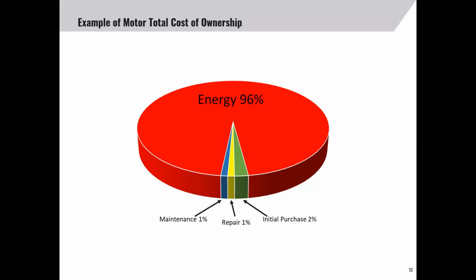There are no NEMA standards for motor efficiency for a manufacturer to meet. As the purchaser, you will be subject to a manufacturer's motor design and the efficiency of that machine. Many companies, when purchasing large horsepower motors, consider these purchases capital expenditures. Most motors above 500 horsepower can cost tens of thousands of dollars in the initial purchase price. Since there are no NEMA standards for these motors, you can have a significantly different electrical consumption to operate the motor. And these are considered capital equipment and expected to have a long life of 10 plus years.